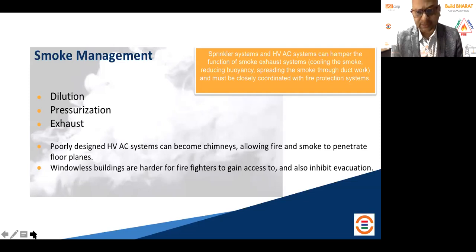The common strategy is dilution. That means the in and out of smoke is maintained, either through natural ventilation or a mechanical ventilation system, such that supply and exhaust are maintained equally. So in case of smoke, it gets diluted with fresh air that has no smoke elements, while the smoke-filled air gets diluted and exhausted. You have smoke-free air coming in and smoke-filled air going out. That's how you manage the smoke and create dilution in the space, whether it's a basement or any other area.